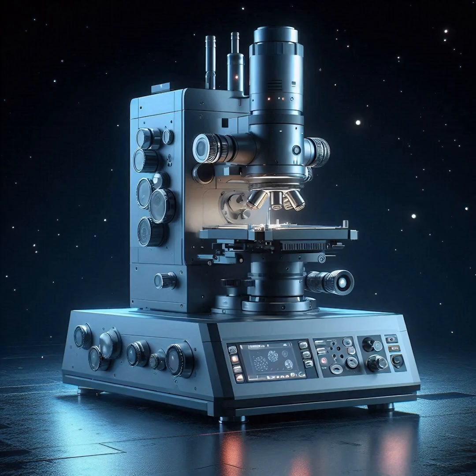To optimize the signal, dedicated backscattered electron detectors are positioned above the sample in a donut-type arrangement, concentric with the electron beam, maximizing the solid angle of collection. BSE detectors are usually either scintillator or semiconductor types.